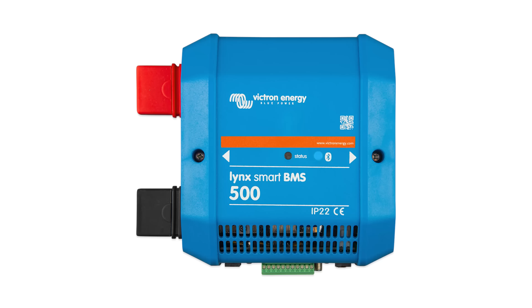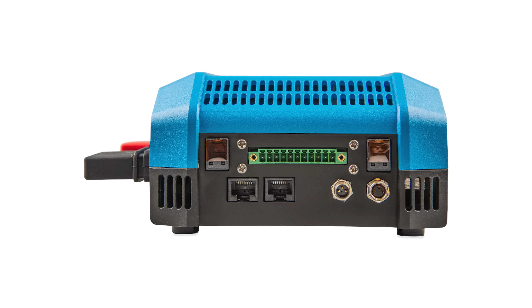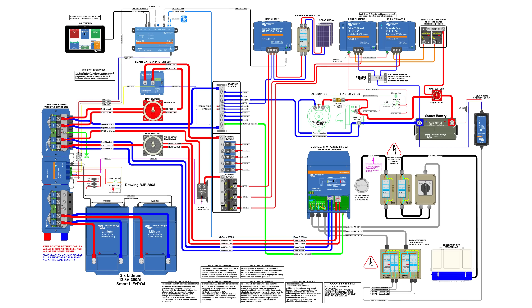One of the first products I would mention is the Lynx Smart BMS. As you know, we have a variety of BMSs, but for the larger system we were still lacking one, and that's the Lynx Smart BMS. It's a BMS which has an integrated contactor, so you will cut off the batteries if something goes wrong with your system. So if you have a low voltage on the cell or a high voltage on your cell, the system itself will shut itself down.